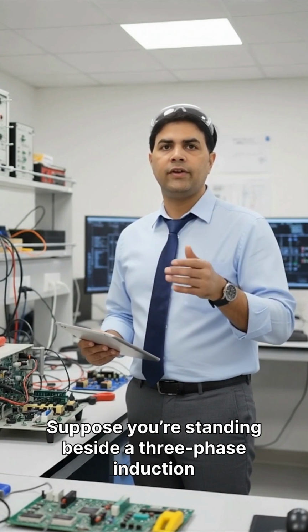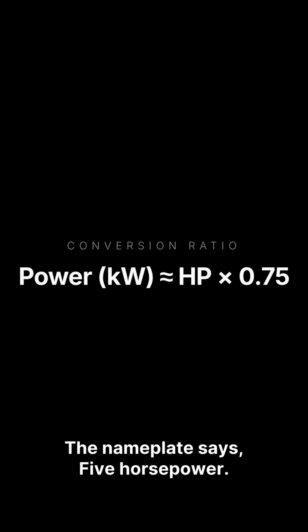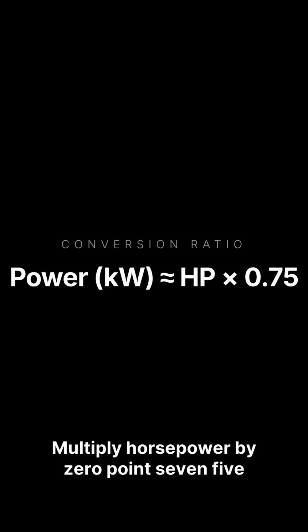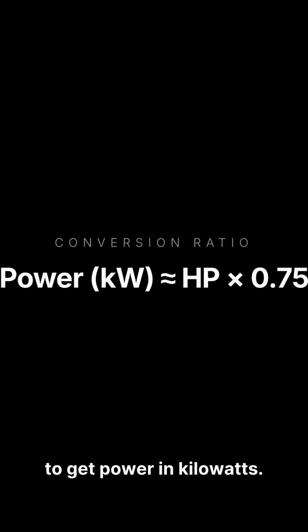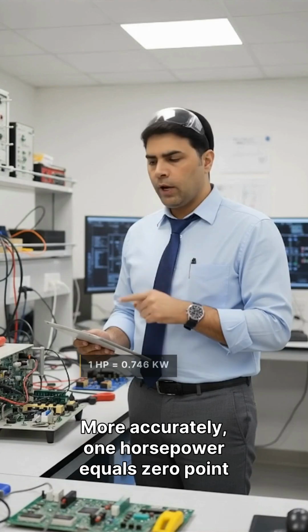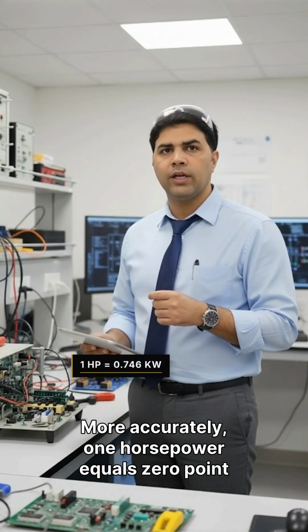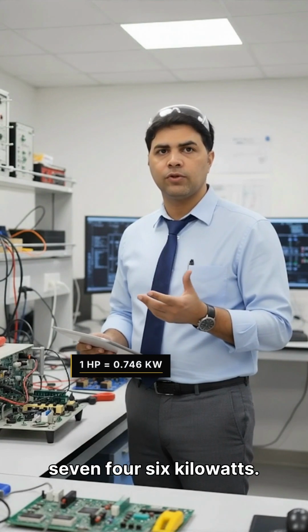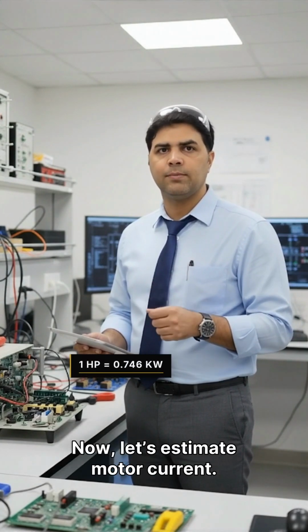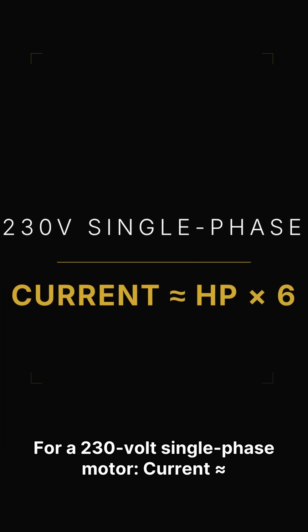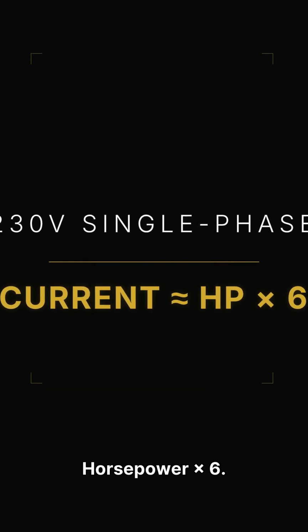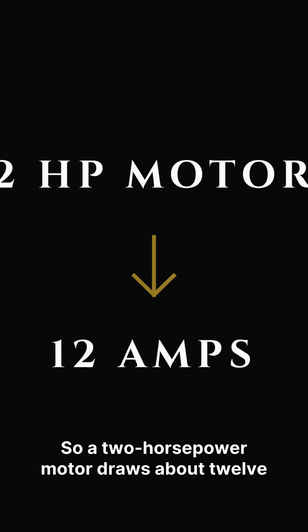Let's move to motors. Suppose you're standing beside a 3-phase induction motor. The nameplate says 5 horsepower. Multiply horsepower by 0.75 to get power in kilowatts. More accurately, 1 horsepower equals 0.746 kilowatts. Now let's estimate motor current. For a 230 volt single phase motor, current approximately equals horsepower times 6. So a 2 horsepower motor draws about 12 amps.